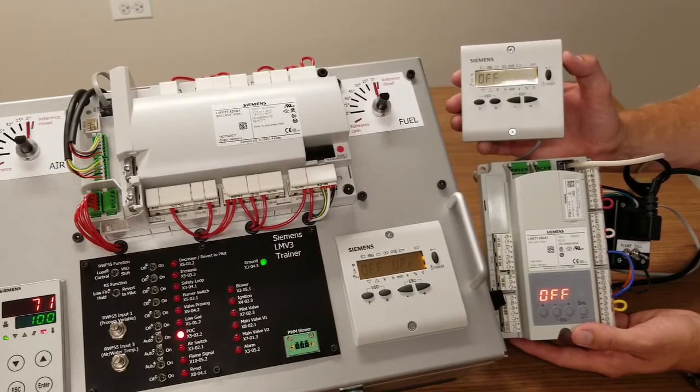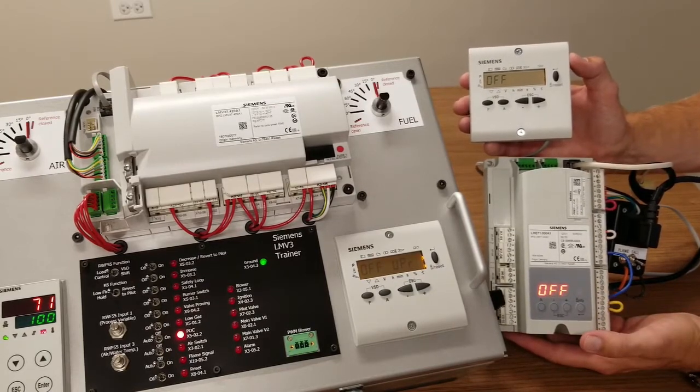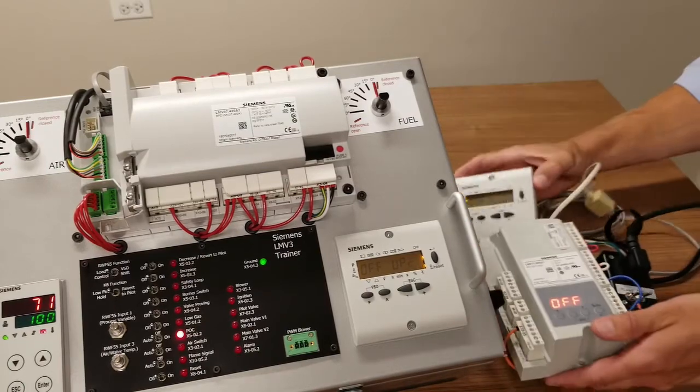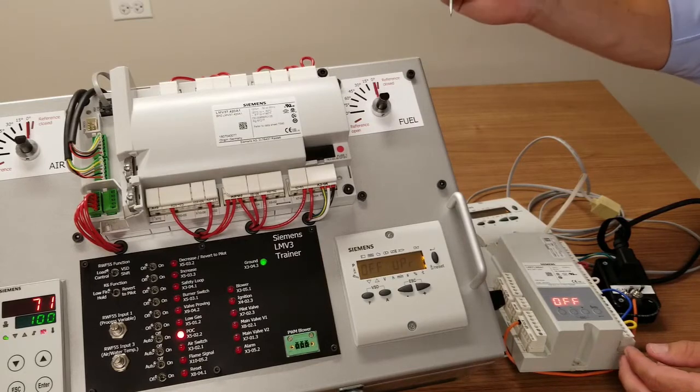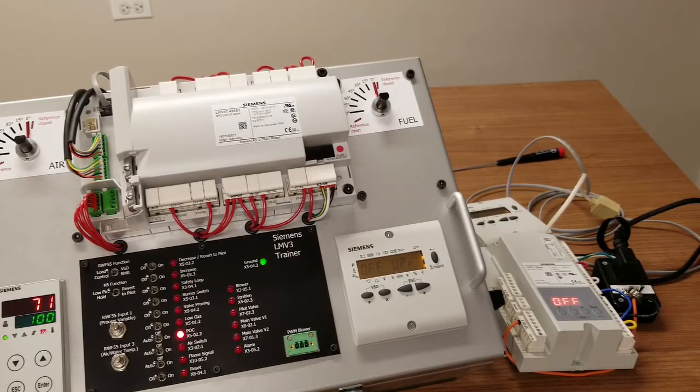You can see the display is backlit and reads off, which mimics what the LME-7's onboard display reads. The LMV3 may often read off UPR, as shown here, if it's not yet programmed, or either of the displays may read a phase or a lockout code, depending on the status of the burner while it's in operation.